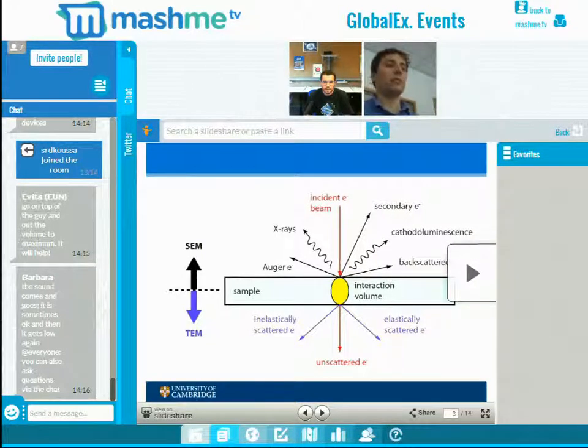Yeah, so you have to distinguish between the transmission electron and the scanning electron microscope. For transmission, you normally only look at samples that are extremely thin, just a couple of hundred nanometers. Otherwise, the electron beam can't penetrate through the sample, and you're not able to see anything. So you have to use samples that are so thin that they are transparent to the electrons. And that's totally different from the scanning electron microscope, the one we showed you the video of a few minutes ago, where you can look at all different kinds of samples.